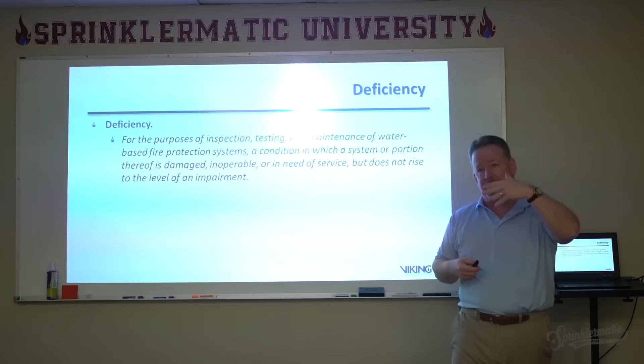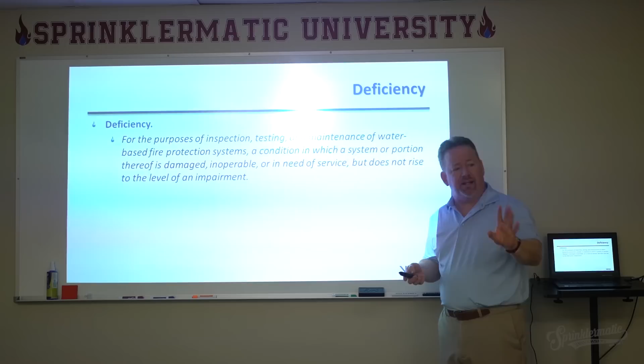When you start to look at sprinklers during an inspection in a building, there can be small amounts of paint, small amounts of schmutz on them, dust and dirt and things like that. We're not really sure if that sprinkler will operate or not, but we're pretty sure it needs to be cleaned. So we're gonna take care of that, but it's not necessarily an impairment.